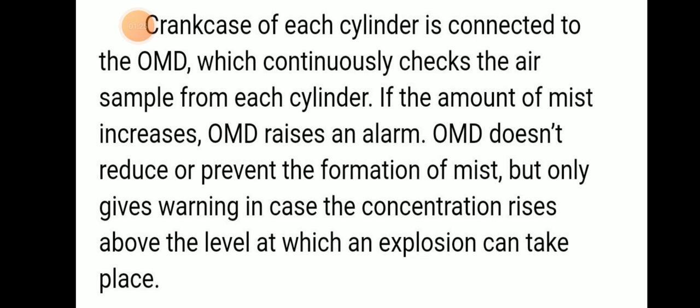The crankcase of each cylinder is connected to an oil mist detector, which will continuously check the air sample from each cylinder. If the amount of mist increases, then the oil mist detector will raise an alarm. The OMD doesn't reduce or prevent the formation of mist, but only gives a warning in case the concentration rises above the level at which an explosion can take place.